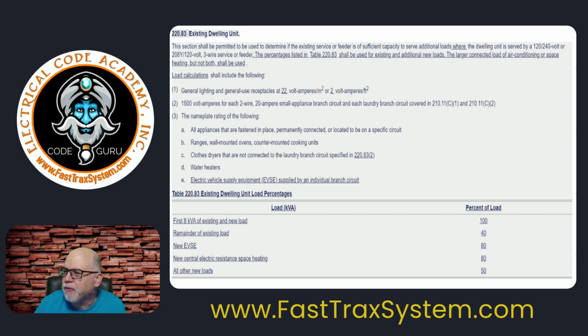It says, this section shall be permitted to be used to determine the existing service or feeder is of sufficient capacity to serve additional loads where, that's important, where the dwelling unit is served by 120/240 volt or a 208Y/120 3-wire service or feeder. It says the percentages listed in Table 220.83 shall be used for existing and additional new loads. The larger connected load of an air conditioning or space heating, but not both, shall be used. Okay, so pretty straightforward, same as it was before.